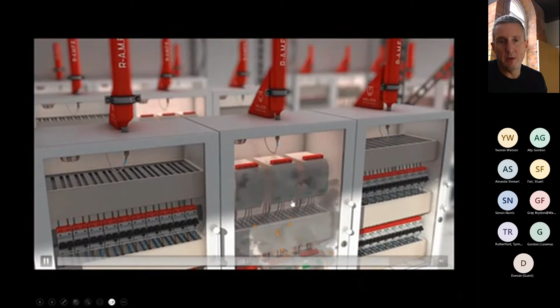The additive that comes out of that system is Novec 1230, which is a non-conductive, non-corrosive product. It has no negative impact on any of the components. If you've got PLCs inside there, or any other high value switches and equipment, this system will not damage those in the event of a fire. Obviously, if the incident catches them, they'll get damaged by the flames until the system goes off. So, going on again to what the system is and how it works.